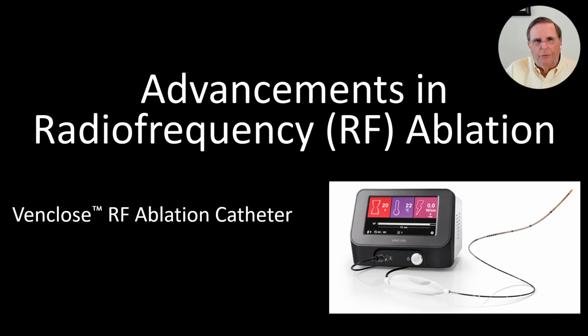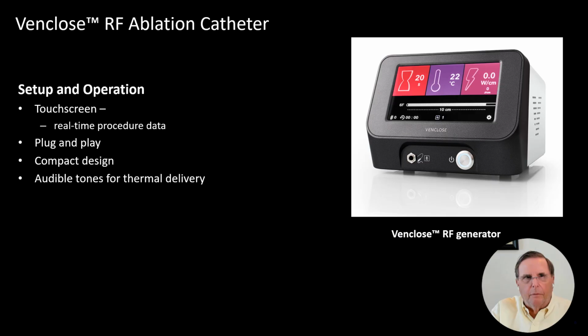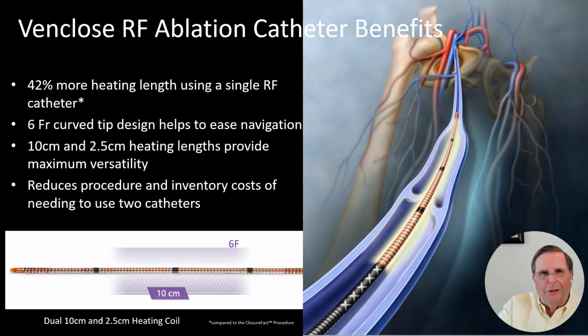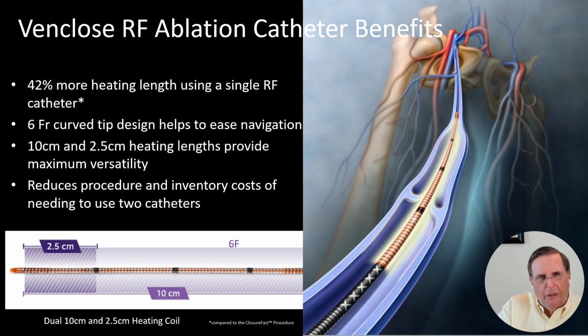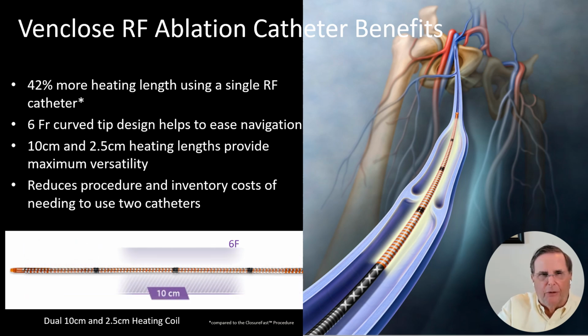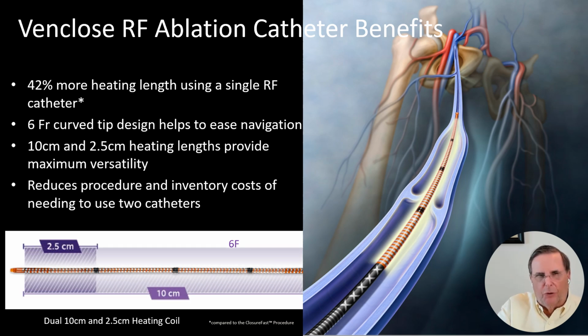So let's look at Venclose. So the generator is really a simple setup, plug and play. The advantages of the Venclose catheter are that it's smaller, it's 6 French versus 7 French. It's better cosmetically, 10 centimeters ablating device versus 7 centimeters, so it's faster. It's got a curved tip which provides maneuverability within the vein. Of importance is 2 different ablating devices within the same catheter, one that's 10 centimeters and one that's 2.5 centimeters. This obviously would reduce the inventory costs and the potential of needing to use 2 catheters.